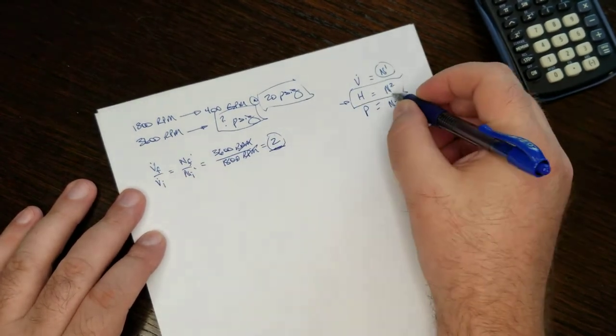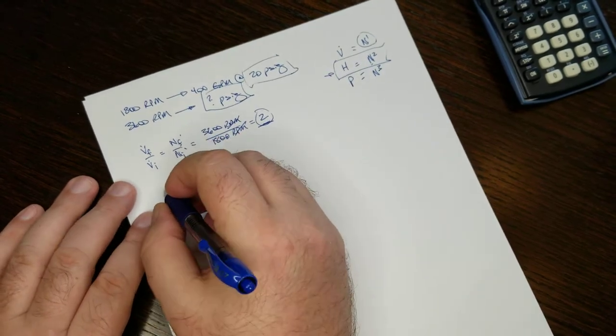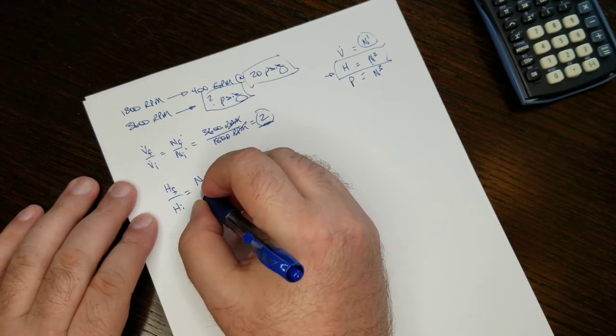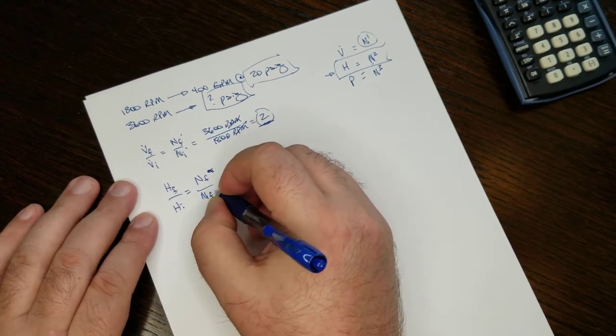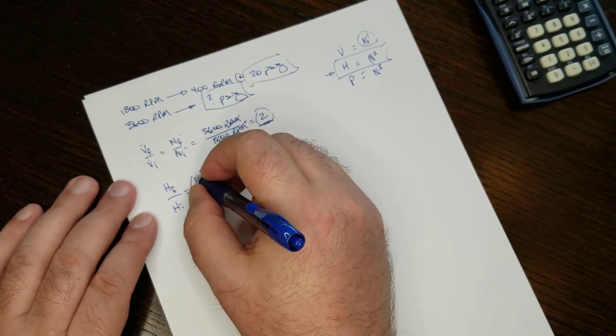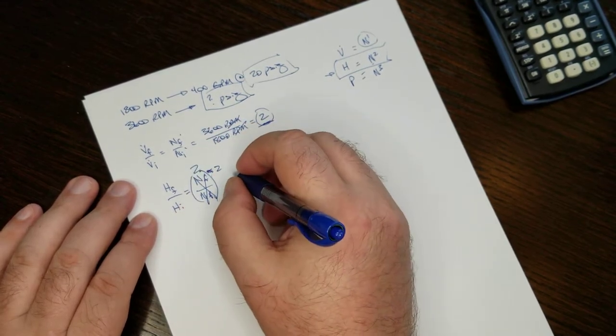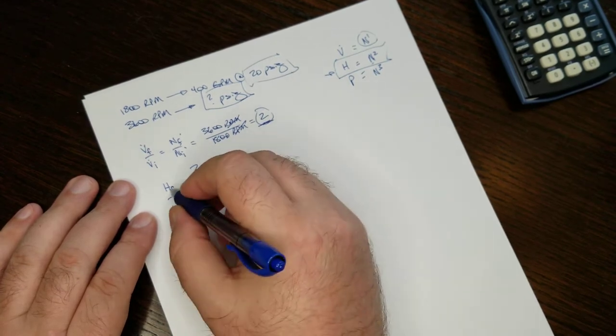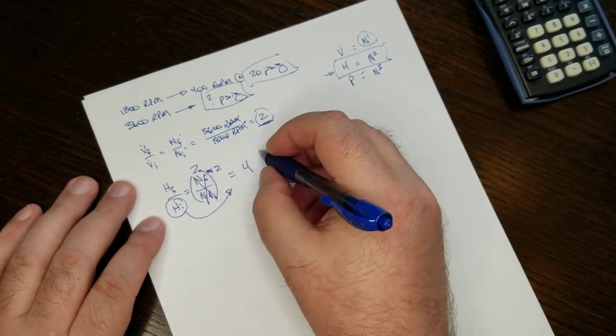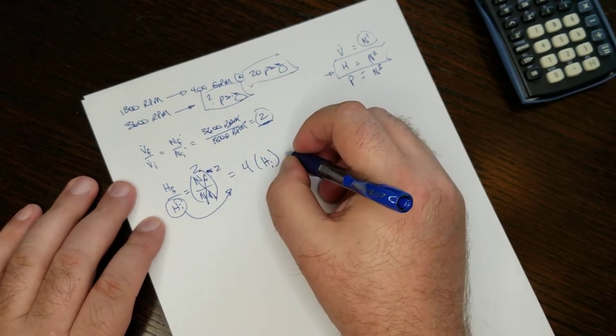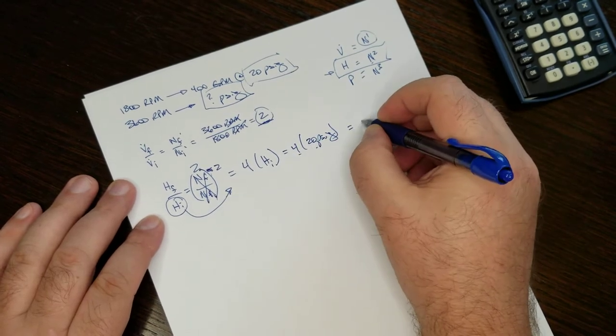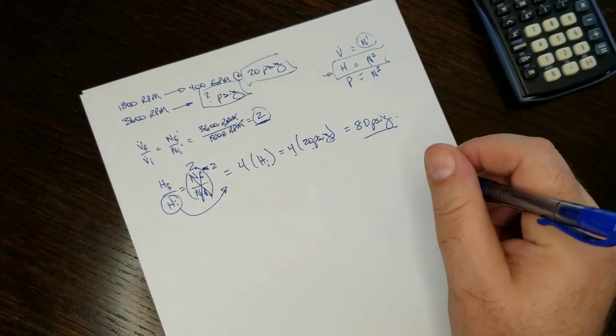And we know that our factor 2 squared... let me not jump ahead. So head final over head initial is equal to speed final over speed initial, and then the whole thing is squared. And we've already done this work here. We know that's 2. And 2 squared is 4. So head final over head initial equals 4. Well, we know this value. So let's move that over here. Multiply times head initial, which is 4 times 20 PSIG, 4 times 20, 80 PSIG. And that's problem one.